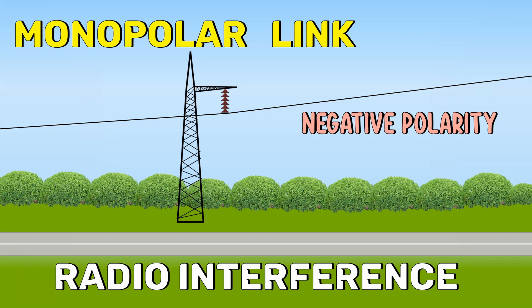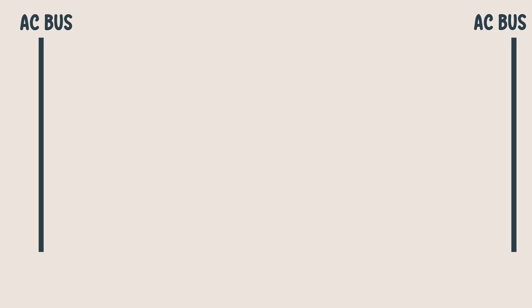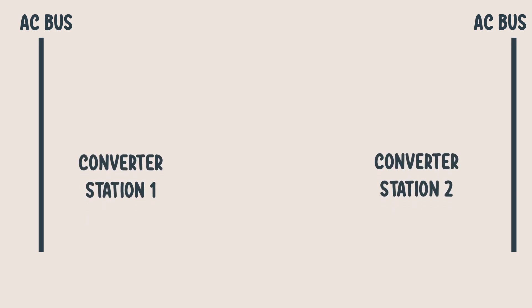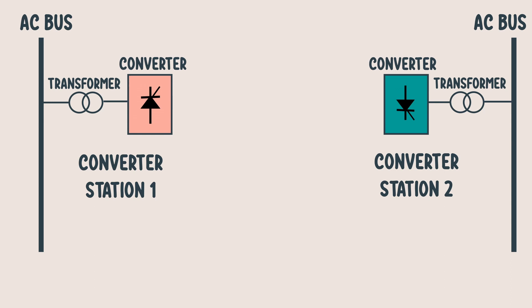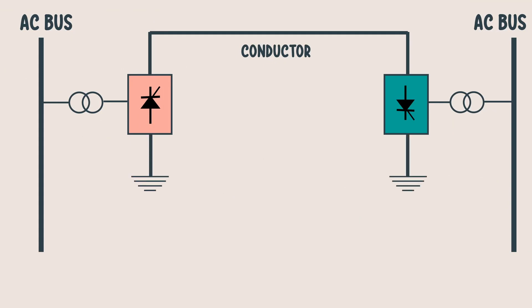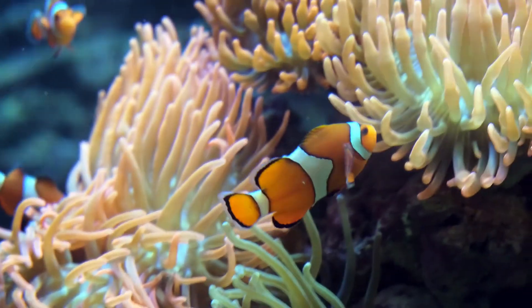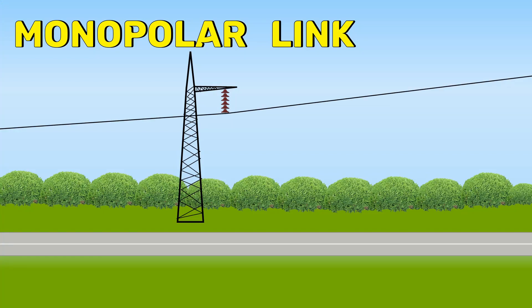Let's see a simple schematic diagram. We have two converter stations, both consisting of a transformer and a converter. In the monopolar link, we have one conductor that links these two stations. But we need a closed path for the current to flow. Therefore, it uses the ground as a return path. In case of submarine cables, seawater is used as the return path. Since it uses only one conductor, it is the most feasible solution in terms of cost reduction.